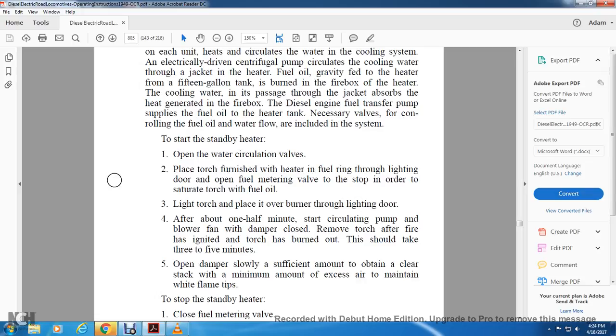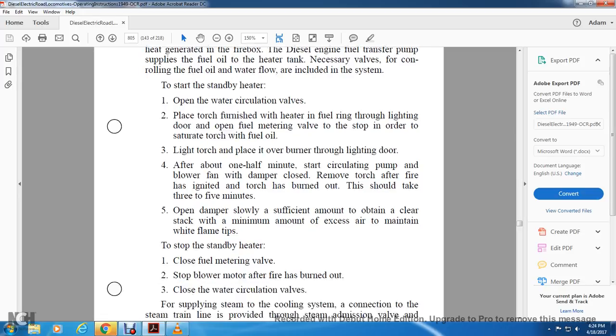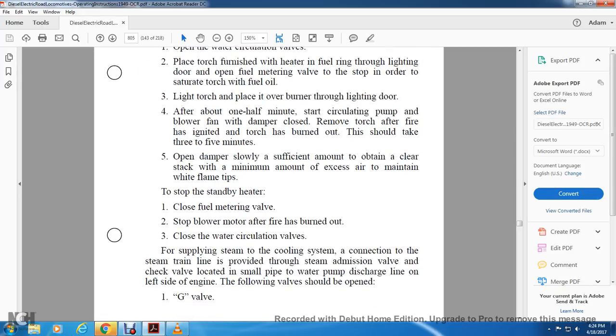This should take 3 to 5 minutes. Open the damper slowly, a sufficient amount to obtain a clear stack with a minimum amount of excess air to maintain the white flame tips. To stop the standby heater, close the fuel metering valve. Stop the blower motor after the fire has burned out. Close the water circulation valve.